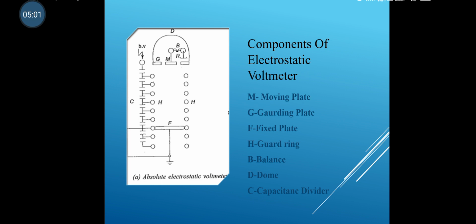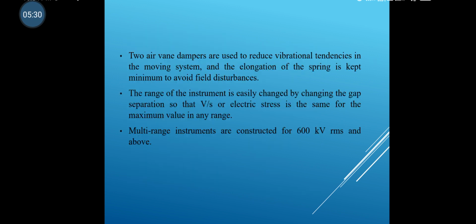D stands for dome. The whole assembly is placed in the hemispherical dome to keep it away from stray capacitances. C stands for capacitance divider, which depends on the level of voltage to be measured. Accordingly, the number of capacitances is adjusted as per the requirement. For that purpose, we are using the capacitance divider there. Two air vane dampers are used to reduce the vibration tendencies in the moving system, and elongation of the spring is kept minimum to avoid field disturbances.